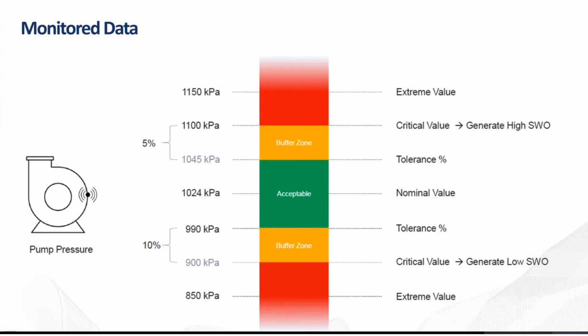When it reaches the buffer zone and the soft limit, we can set algorithms. If it reaches it once, it can generate an alert or notification. If it reaches it 3 times, 5 times, 10 times, it is all down to the process that the client requires. But of course, if it reaches the hard limit, the critical value, then it automatically can generate a work order for the technician to go and check it out as soon as possible.